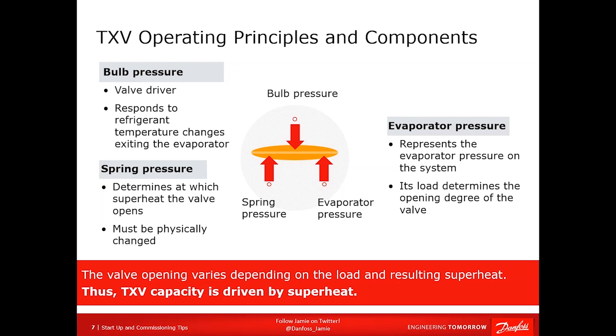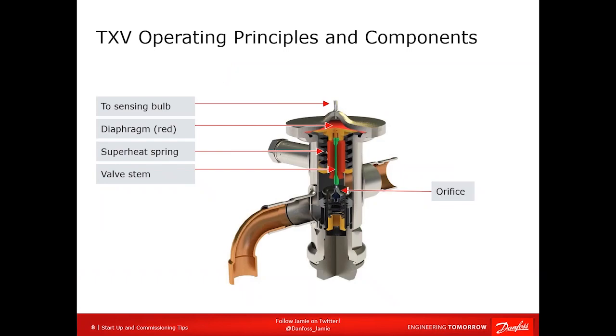So superheat is required in order to raise the bulb temperature and pressure to overcome those two. So when we say the TXV has a factory superheat setting of 7 degrees, that means the TXV will not even open until you have 7 degrees of superheat, because that's how much temperature rise above saturation is required to increase your bulb pressure enough to overcome those two forces. Without that spring pressure, you wouldn't have superheat. You just have a flooded evaporator and a flooded compressor. So the load on the evaporator, the amount of superheat you have, determines the opening of the TXV.